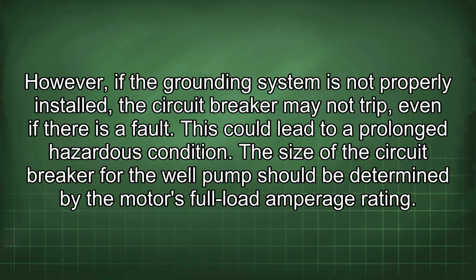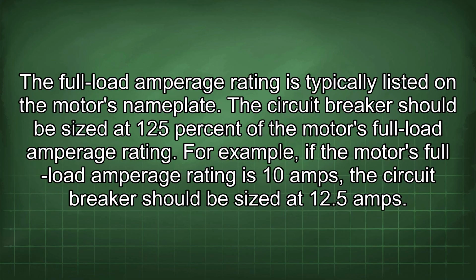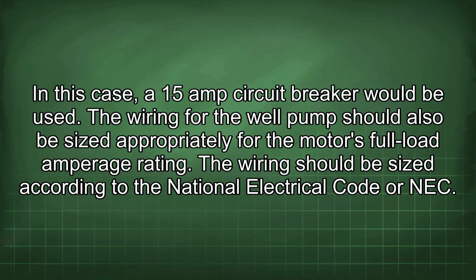However, if the grounding system is not properly installed, the circuit breaker may not trip, even if there is a fault. This could lead to a prolonged hazardous condition. The size of the circuit breaker for the well pump should be determined by the motor's full load amperage rating. The full load amperage rating is typically listed on the motor's nameplate. The circuit breaker should be sized at 125% of the motor's full load amperage rating. For example, if the motor's full load amperage rating is 10 amps, the circuit breaker should be sized at 12.5 amps. In this case, a 15 amp circuit breaker would be used.